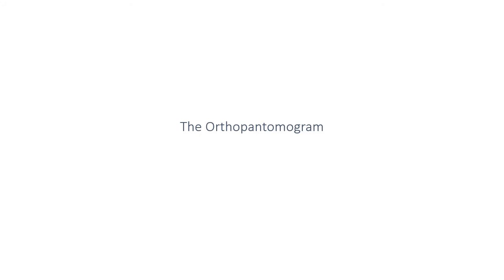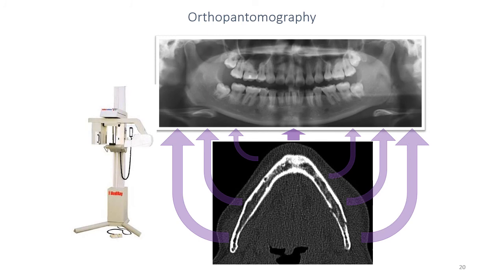The orthopantomogram — or OPG — works by exposing only a small area of the image receptor at one particular time. Over the course of the exposure, the x-ray tube and image receptor rotate around the patient, segment by segment. Subsequently, the curved structure of the mandible is shown as a flat structure across the plane of the image receptor.